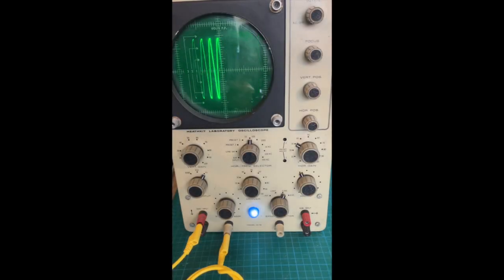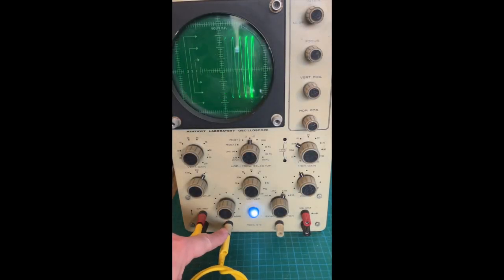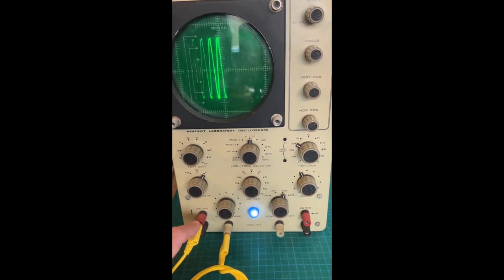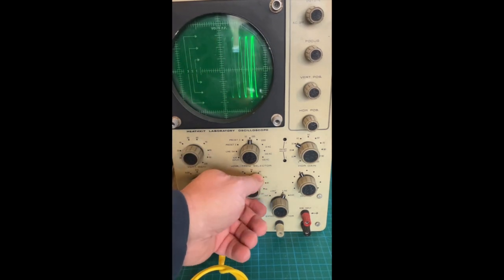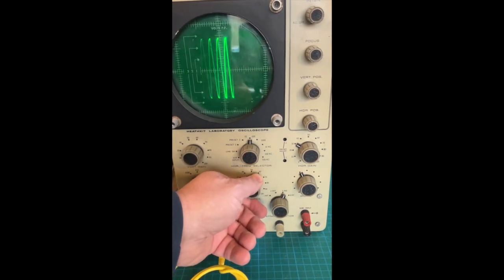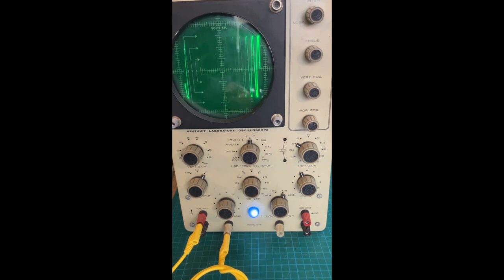So here I'm showing the 60 hertz line frequency output, which is 1 volt peak to peak, which the scope makes available, going directly into the vertical. I've chosen the lowest possible frequency of sweep. 1, 2, 3, 4, 5, 6, 7, 8, 9, 10, 11. So that's a sweep frequency of something like 5 or 6 hertz.